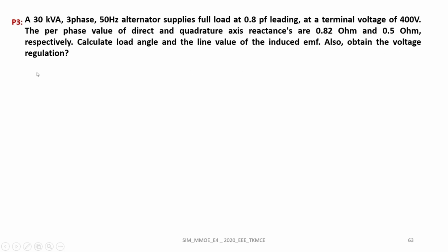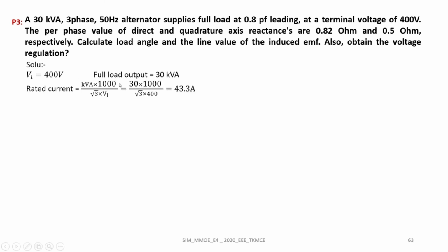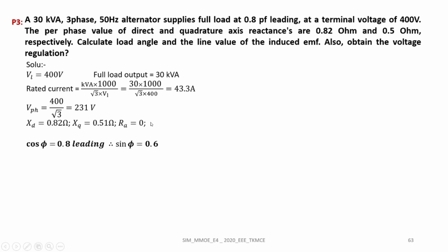Coming to the solution, here the line value of the voltage is 400 volt and the full load output is 30 kVA. Rated current is calculated from line value and full load output as 43.3 ampere and phase voltage is 231 volt. Armature resistance is neglected and XD is given as 0.82 ohm and XQ is given as 0.51 ohm. As cos phi is 0.8, sin phi is 0.6.